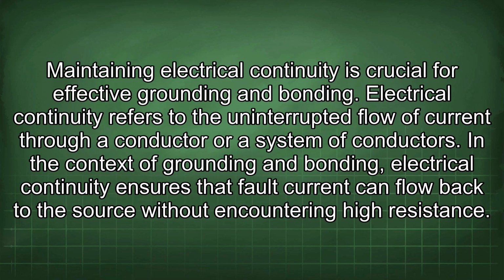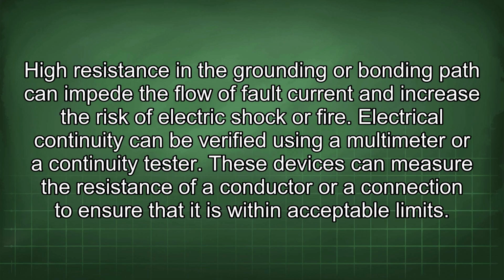Maintaining electrical continuity is crucial for effective grounding and bonding. Electrical continuity refers to the uninterrupted flow of current through a conductor or a system of conductors. In the context of grounding and bonding, electrical continuity ensures that fault current can flow back to the source without encountering high resistance. High resistance in the grounding or bonding path can impede the flow of fault current and increase the risk of electric shock or fire.